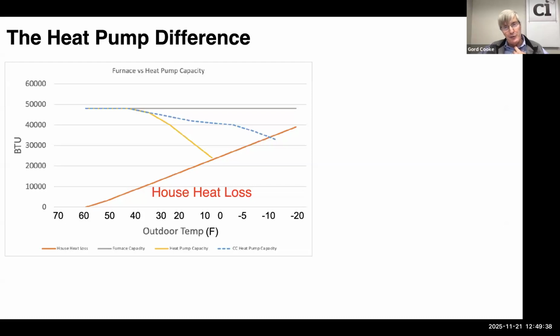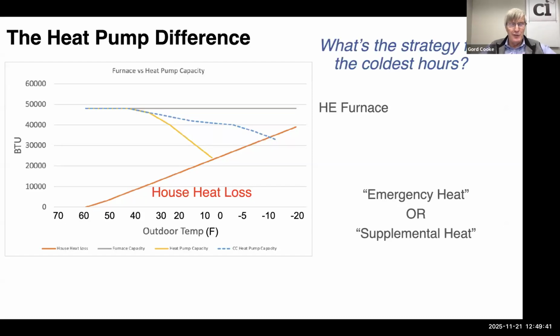And the big difference is furnaces. The high efficiency furnace, regardless of what the temperature is outside, that's the gray line. It did what it needed to do. It gave you that 48,000 BTUs. The standard old heat pump from 20 years ago, that's the one in gold. Notice how its performance drops off. Its capacity drops as it gets colder outside, and in fact, at about 10, 12 Fahrenheit, they cut off altogether. You had no energy whatsoever, and you needed emergency or supplemental heat to make up that difference.